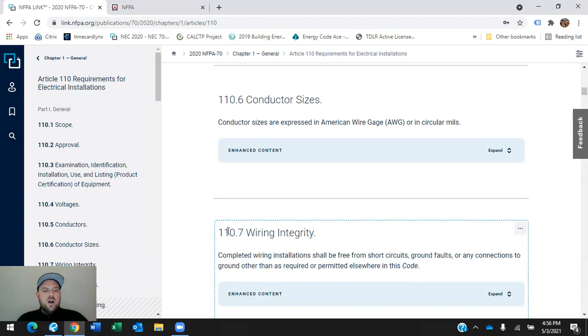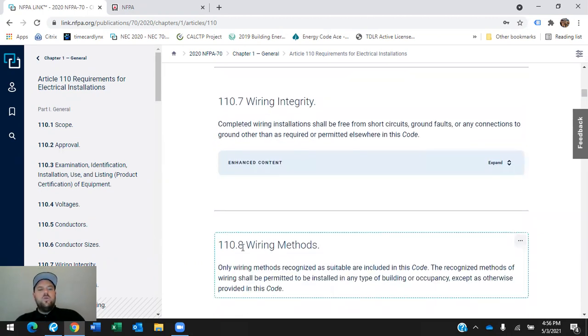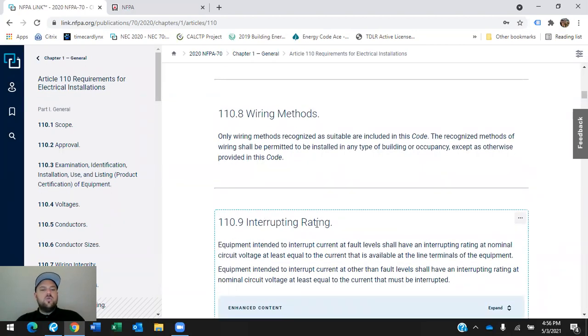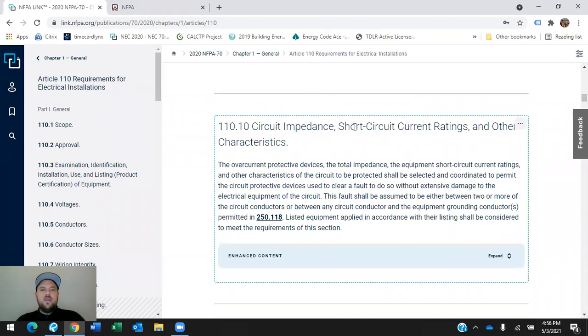AWG, or circular mils. 110.7, wiring integrity. 110.8, wiring methods. 110.9, interrupting rating. 110.10, circuit impedance, short circuit current ratings, and other characteristics. The overcurrent protective devices, the total impedance, the equipment short circuit current ratings, and other characteristics of the circuit to be protected shall be selected and coordinated to permit the circuit protective devices used to clear a fault to do so without extensive damage to the electrical equipment of the circuit. This fault shall be assumed to be either between two or more of the circuit conductors, or between any circuit conductor and the equipment grounding conductor permitted in 250.118.